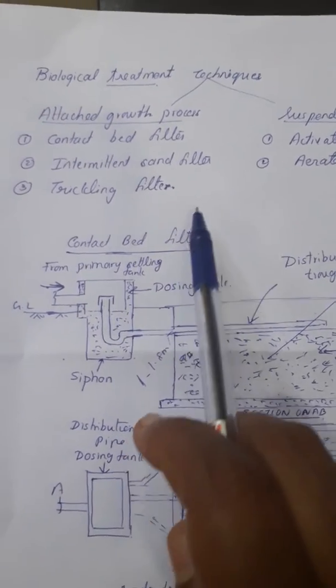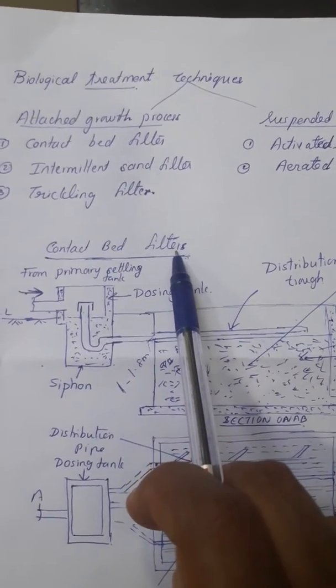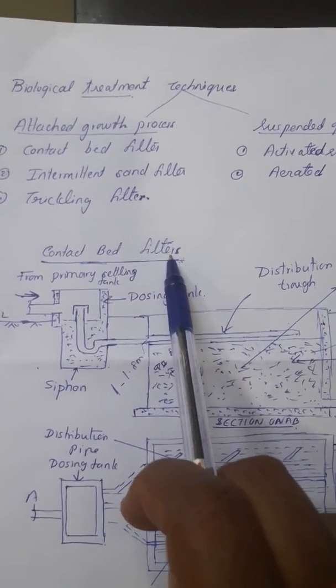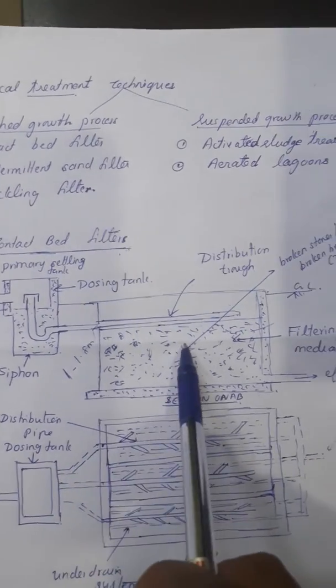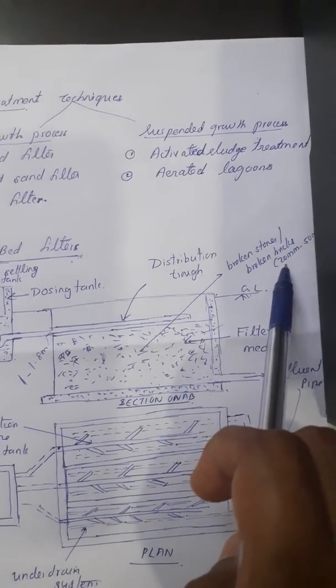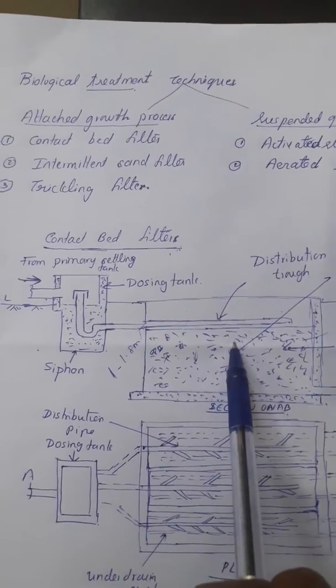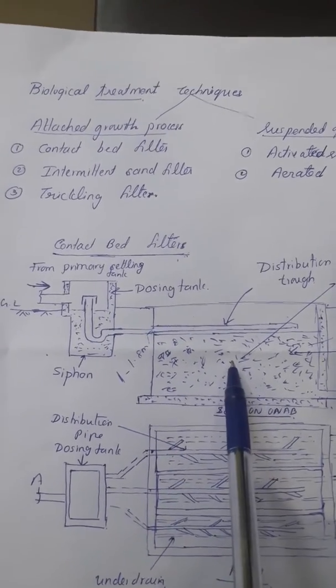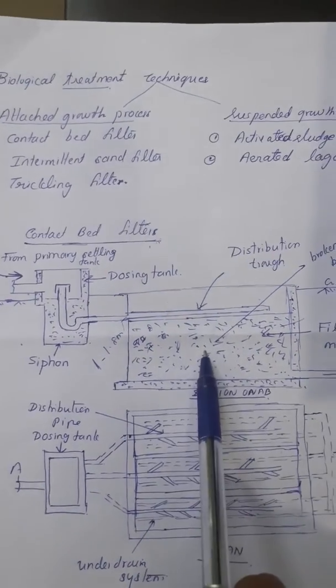Earlier we discussed the intermittent sand filter. This contact bed filter is similar to the intermittent sand filter in construction, except that in contact bed filter we are using broken stones or broken bricks of 20 mm to 50 mm size materials. Here we are using coarser materials compared to the finer materials used in intermittent sand filter.